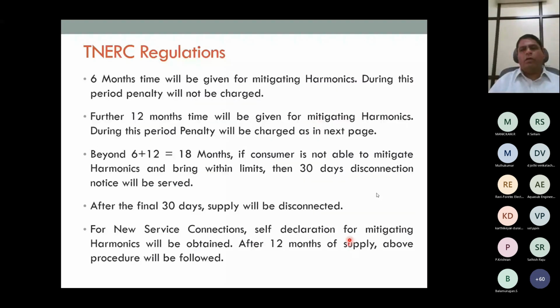So how much time will a consumer get? 6 months time will be given after measurement. They serve you a notice. If you are complying, they'll state that this consumer is complying. If the consumer is not complying with the regulations, they'll give you a notice, and 6 months time will be given. During this 6 months, they will not charge any penalty. After 6 months, a further 12 months will be given for the consumer to mitigate harmonics. During this period only, penalty will be charged.